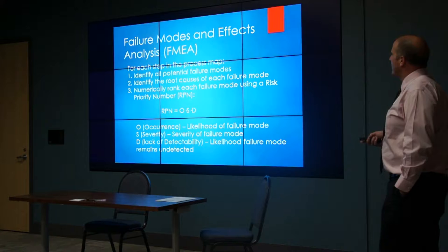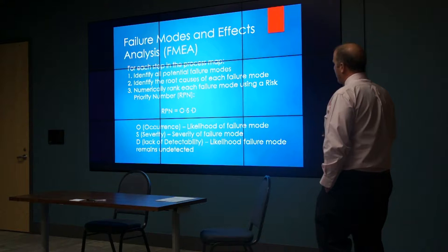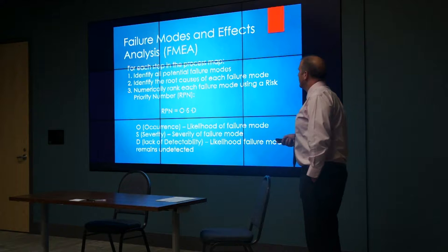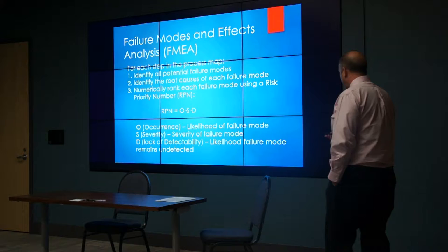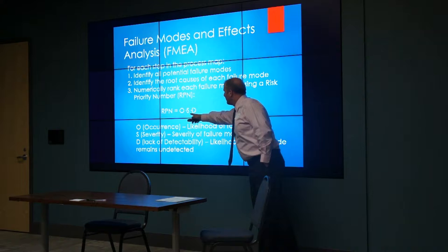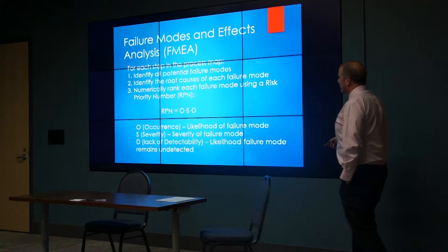Once you have a process set up, the next step is to do a failure mode and effects analysis, or FMEA. In FMEA, you go through each step of the process map and identify all potential failure modes—what could go wrong in this step. Then you identify the root causes for each failure mode—why would this happen. Then you numerically rank each failure mode using what's called a risk priority number, or RPN, which is the product of three separate numbers: O for occurrence, S for severity, and D for detectability, or lack of detectability.